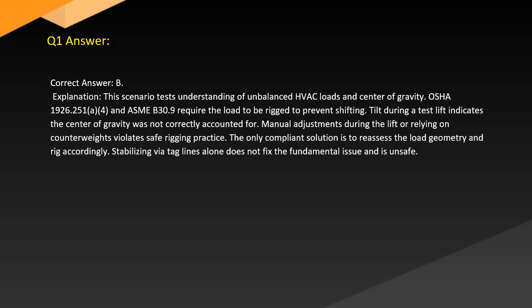Answer. Correct answer: B. Explanation. This scenario tests understanding of unbalanced HVAC loads and center of gravity. OSHA 1926.251(a)(4) and ASME B30.9 require the load to be rigged to prevent shifting or tilt during the lift. A test lift indicates the center of gravity was not correctly accounted for.